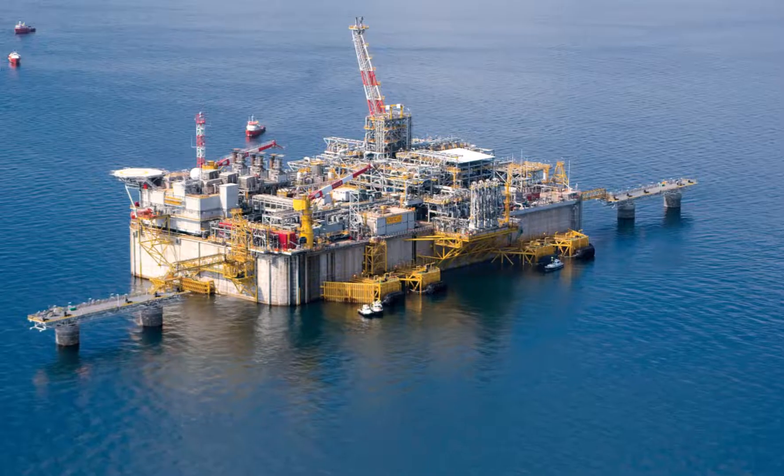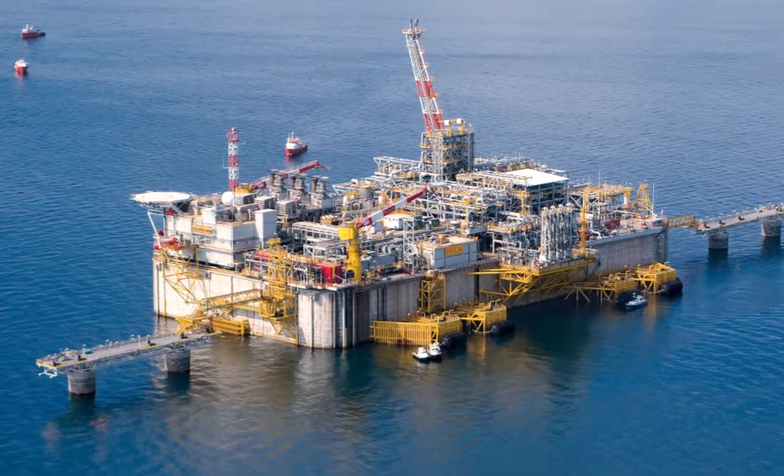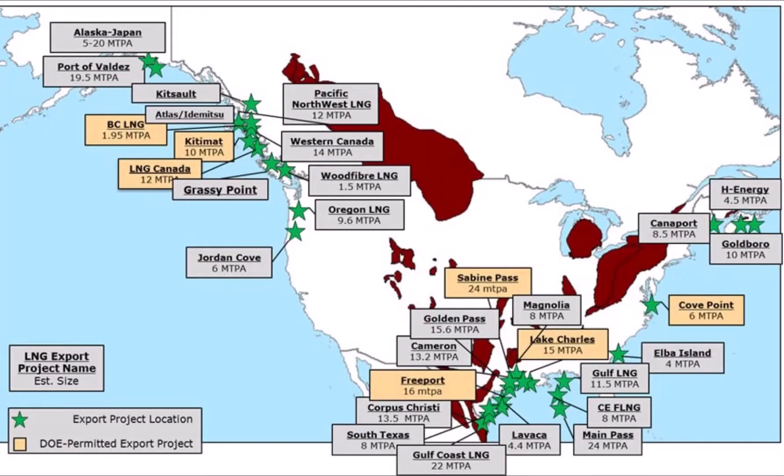A key safety difference between natural gas and LNG: while natural gas rises when it leaks to the atmosphere, LNG vapors are initially heavier than air and spread along the ground when they leak, leaving them open to potential ignition sources and flashback resulting in a great explosion. This is another reason LNG terminals are located along waterways — both for export convenience and safety. Some are completely offshore, like the Adriatic terminal, while others are docked inland; process safety, risk assessment, and economics determine exact locations.